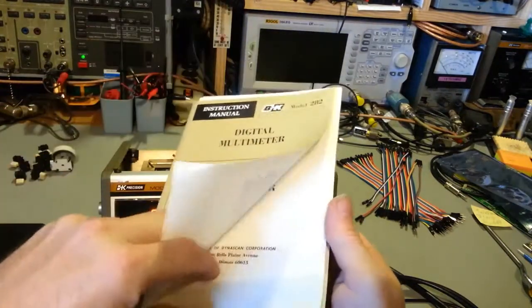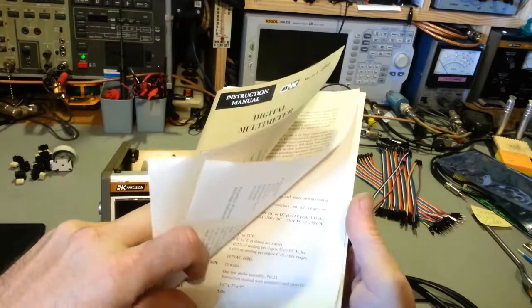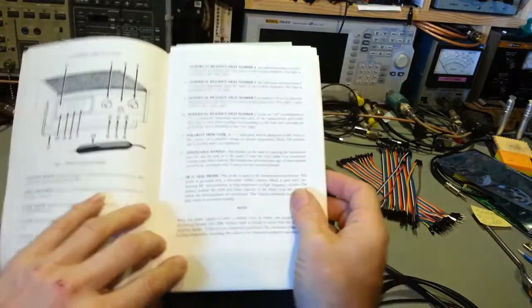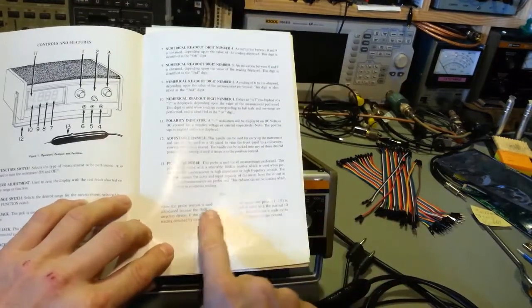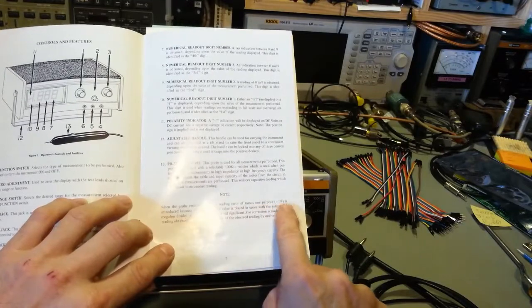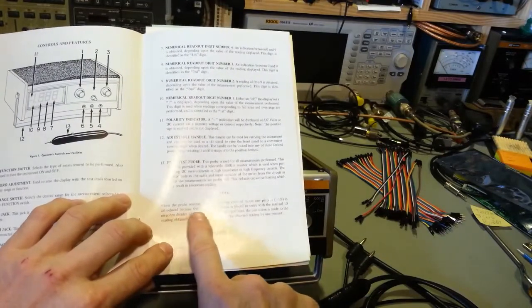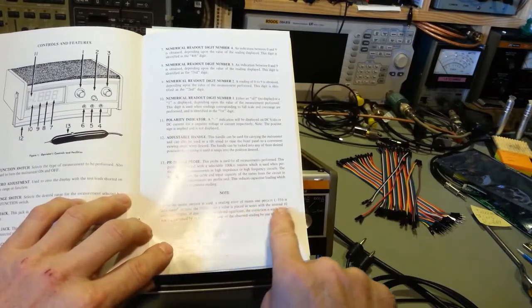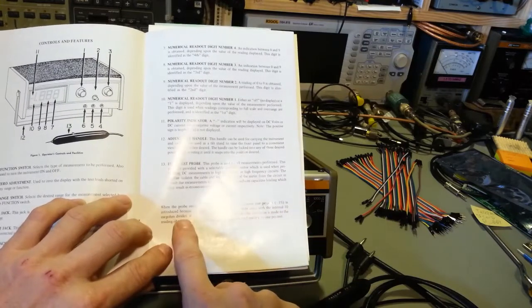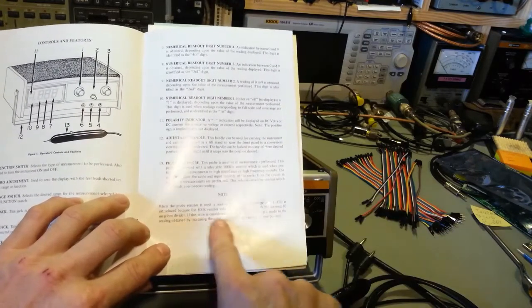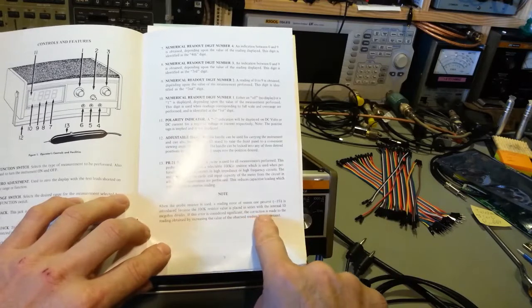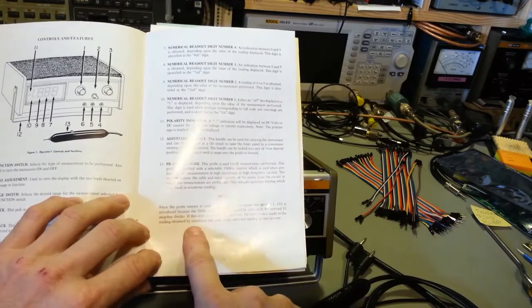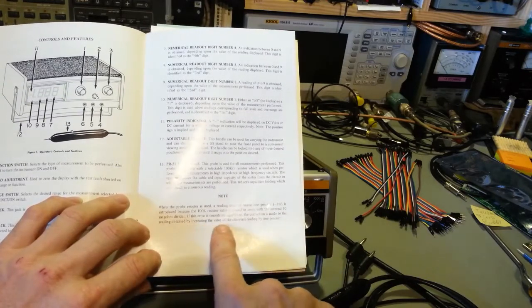About the probe - when the probe resistor is used, a reading error of -1% is introduced because the 100K resistor value is placed in series with the internal 10 mega ohm divider. If this error is considered significant, correction can be made by increasing the observed reading by 1%.